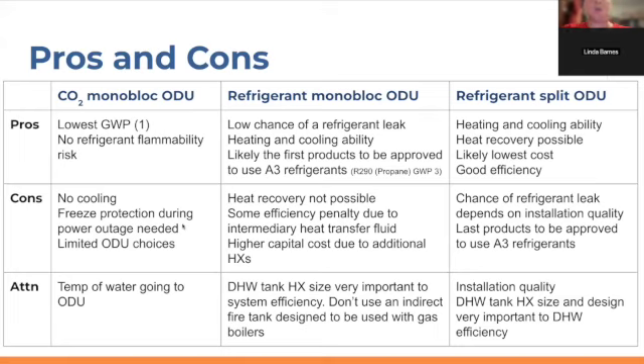But one of the cons of CO2 monoblock outdoor units is that there are very few manufacturers of these outdoor units, and those manufacturers produce very few variations. To my knowledge, maybe only two manufacturers make them, and each of them only makes like one or two models. So there may be only like four different variations of CO2 monoblock outdoor units in existence currently.